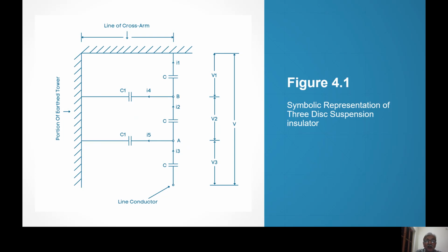Therefore, if you really measure the voltage across the disks, V1, V2, V3 across 3 disks, the total voltage V is obviously line voltage divided by root 3. But V1 equal to V2 equal to V3 equal to V by 3 is not correct. V3 is highest, V2 is medium, and V1 is the lowest. And now, because of this, it is quite possible that if V3 is so high that the shunt capacitance C cannot withstand it and it will break down, then the total voltage will be stressed on the two other capacitances. Obviously, two capacitances cannot withstand that stress, and then the whole insulator string will fail.